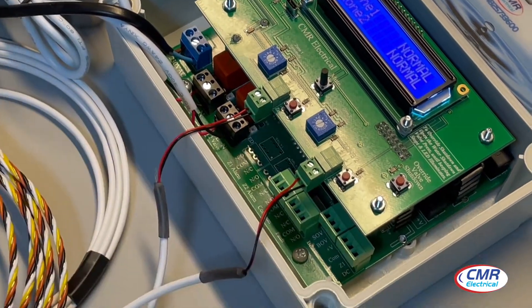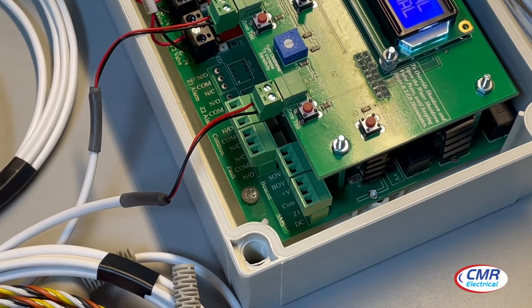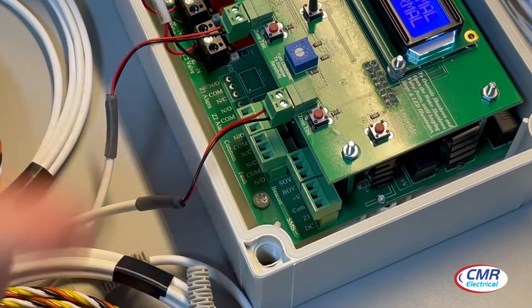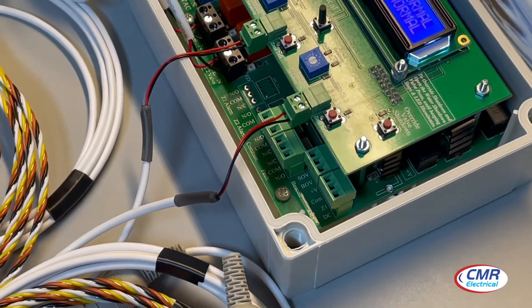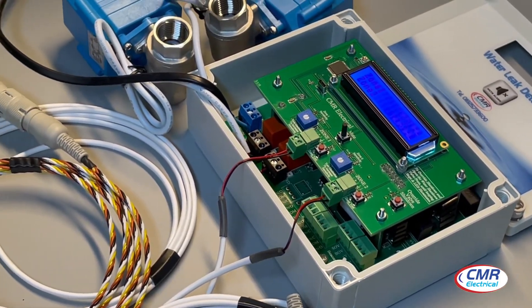Moving along, you have a common alarm volt-free contact. This is standard with the LD2-3 product. This can also be connected to a BMS system. When the panel goes into alarm, it will notify the BMS system that an alarm has occurred.